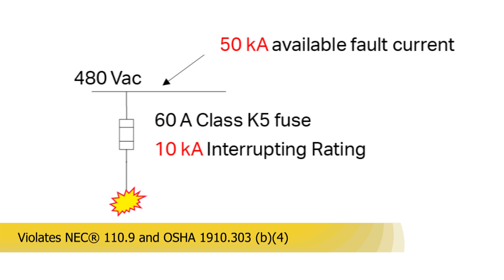The following test shots will demonstrate the destructive nature of short circuit events and the importance of proper interrupting rating. These tests will be conducted on a 480 volt circuit with an available fault current of 50,000 amps. It is not the intent to degrade any equipment, but rather show the possible result of misapplication of the equipment used. The first test will show two 600 volt general purpose fuses with a 10,000 amp interrupting rating. A short circuit is applied directly on the load side of the fuses.